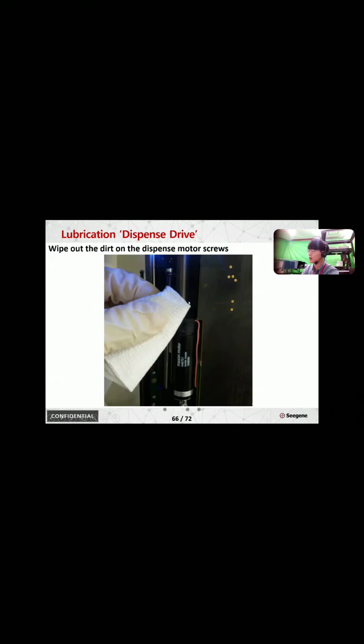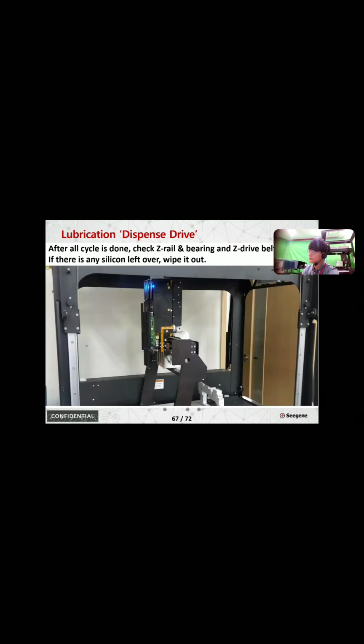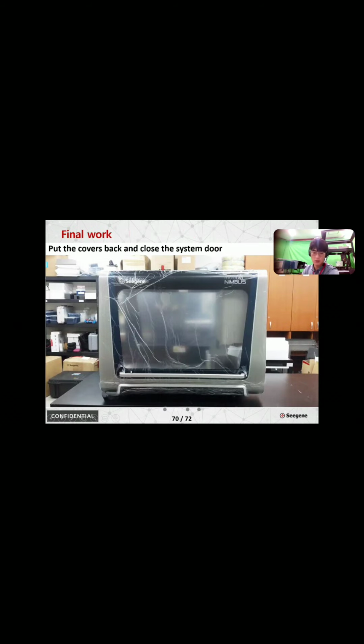And then wipe out the dirty oil, but do not grab the spindle of the pipette head because it is very easy to break when we grab the dispense spindle of the pipette head. Just leave the paper close to the spindle. The oil will be absorbed into the paper. Okay, and then close the door. The lubrication is done. When you do the lubrication thoroughly, from the 2 X-rails, 4 pulleys, and the belt for the X movement, and channel, squeezer motor, dispense motor, it will take about 1 hour. Okay, but for maintenance, the lubrication is very important.